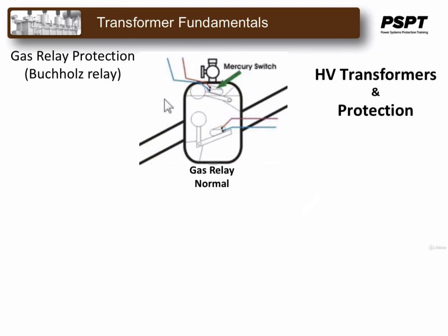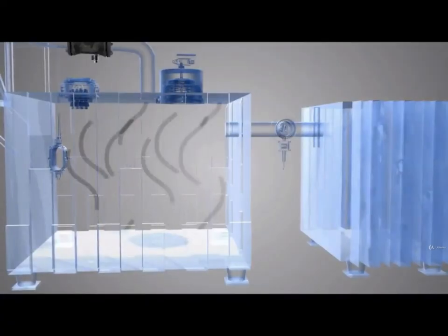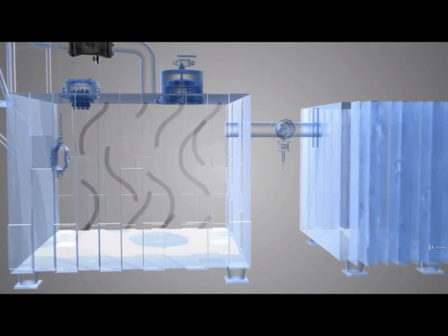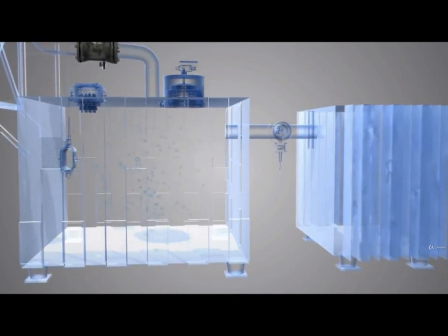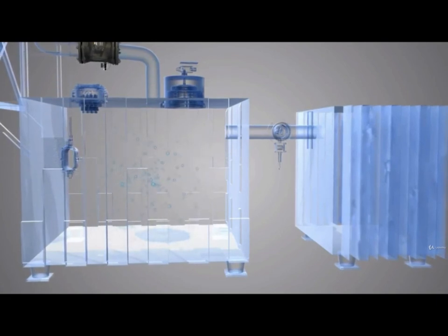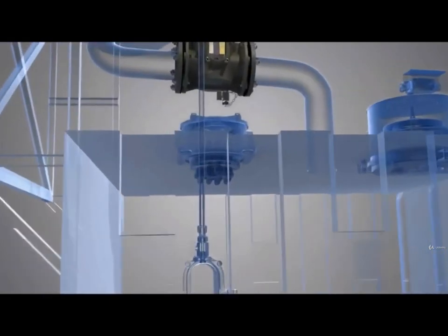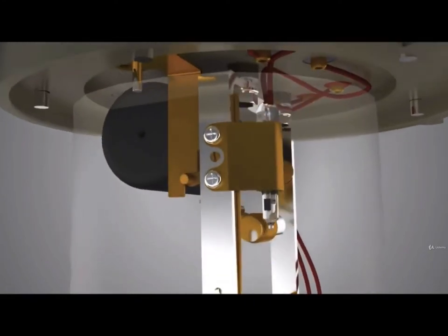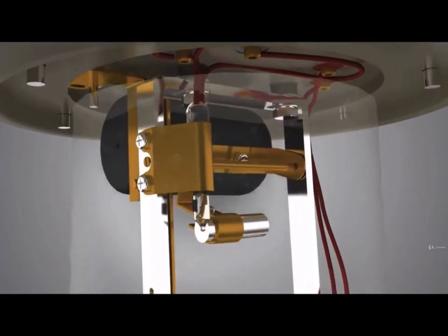Under normal conditions, there is little or no gas in the Buchholz relay, and the float keeps the mercury switch open. On a slow accumulation of gas, due perhaps to slight overload, gas is produced by decomposition of the insulating material as well as the oil. These gases will slowly rise in the transformer and accumulate in the top of the relay. As more and more of these gas bubbles collect, they will force the oil level down in the relay. The float switch in the relay will close and initiate an alarm signal.